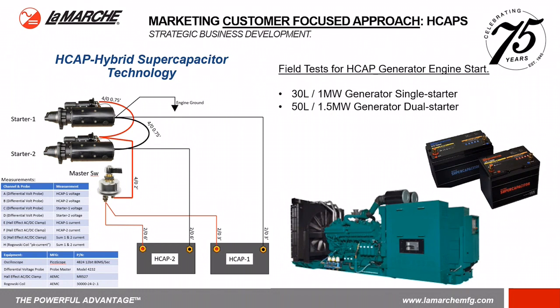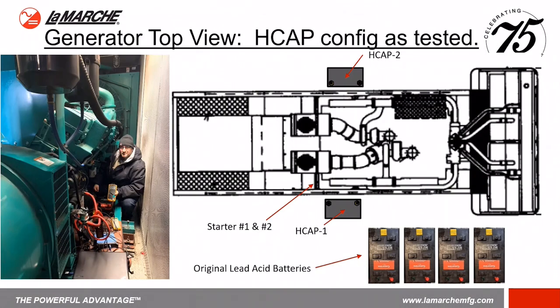Their system consisted of a 50-liter, 1.5 megawatt generator where they had dual starters. And that's where they had 4 sets of batteries, 8Ds, and they selected to go with one HCAP, two HCAPs on each starter versus 4 batteries. Here was their initial setup, and as you can see, they replaced them with HCAP 1 and HCAP 2 to start both starters.